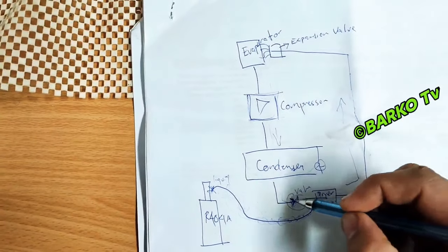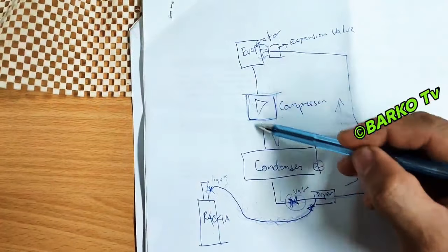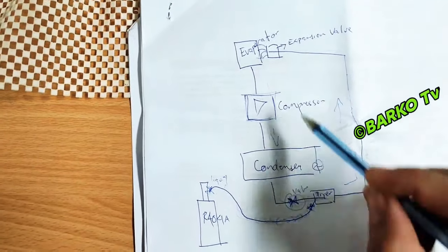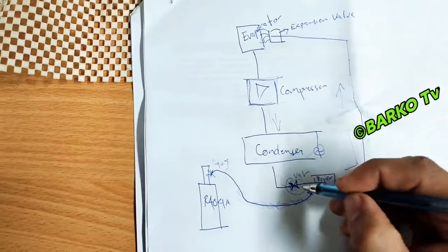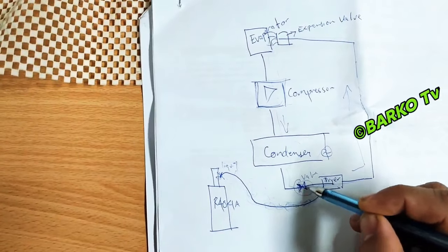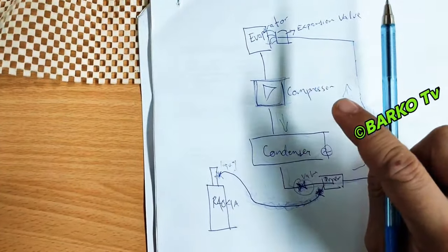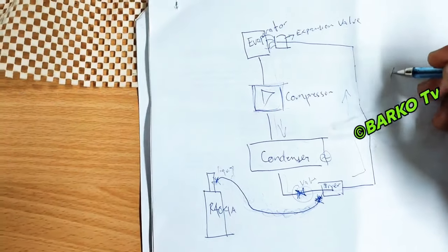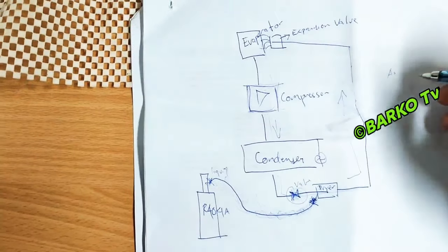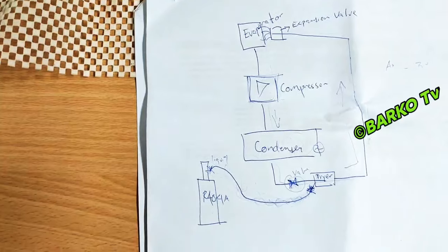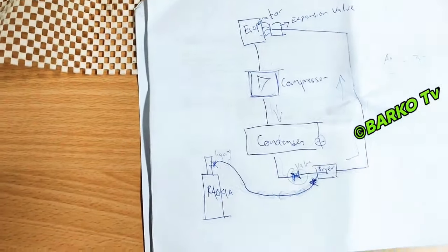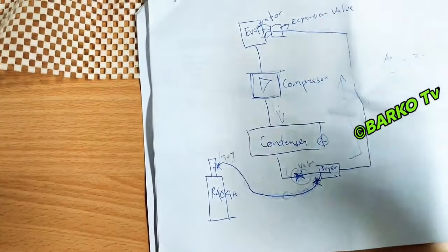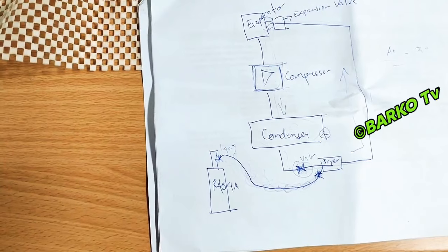And then lastly, on the last cycle, when this compressor is running, just close this valve so that all of this refrigerant is emptied. And then after this compressor stops with low suction triggered, close this valve and then open this valve so that the pressure rises up again, and then start the system. Additional information, anti-recycling again is set to about 30 minutes for this system. If you need to start again, just turn off the control power and then press start. Anti-recycling time is activated during low suction. Low suction is triggered. Okay.